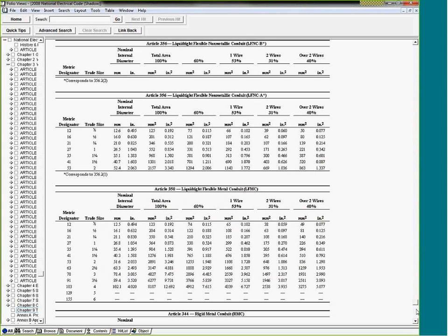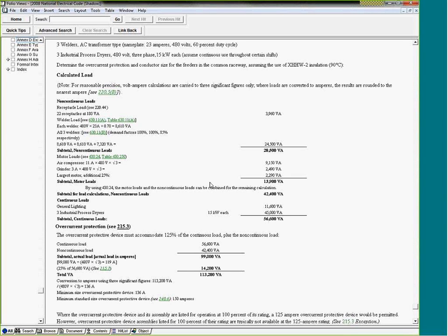And I know I'm almost running out of time, so I might not be able to give you the poll, guys. But any questions, I will make sure that you know how to do that. Any questions? Questions on how to use it? You take the cross-sectional area of the conductors you have, and then you go to the table for that particular conduit that you want to fill, and find yourself a conduit with that particular size. If all your conductors are the same size, you don't need to do that.